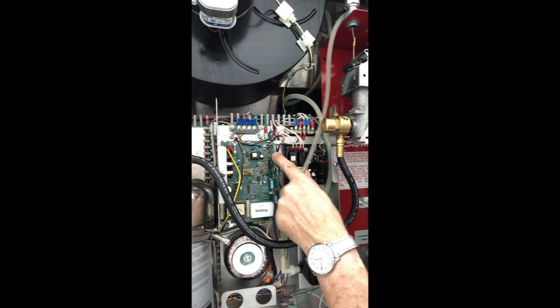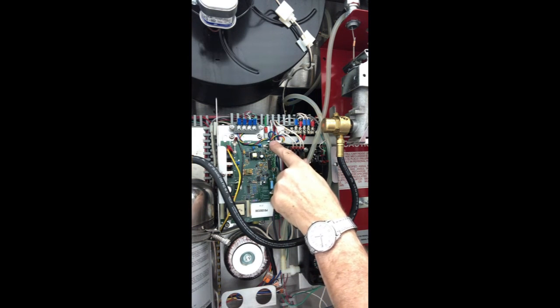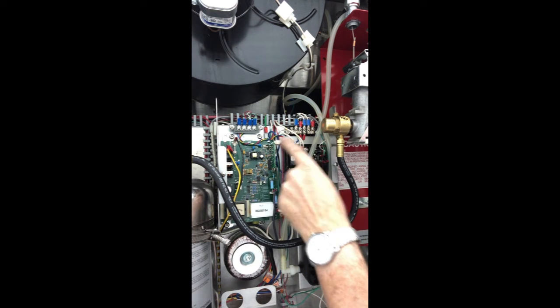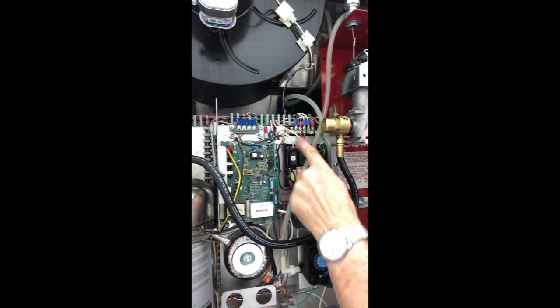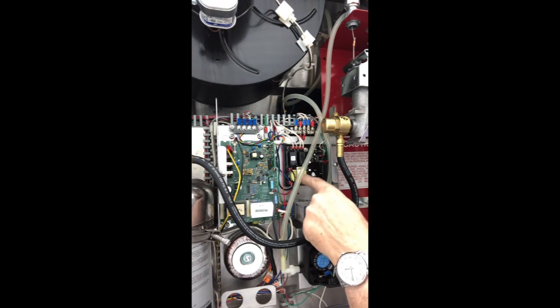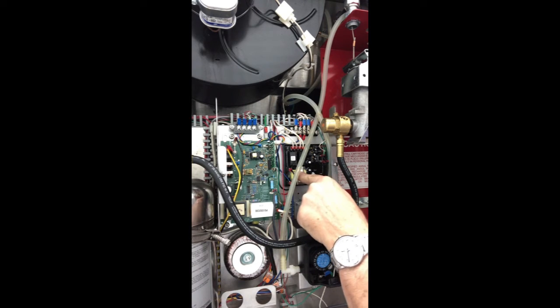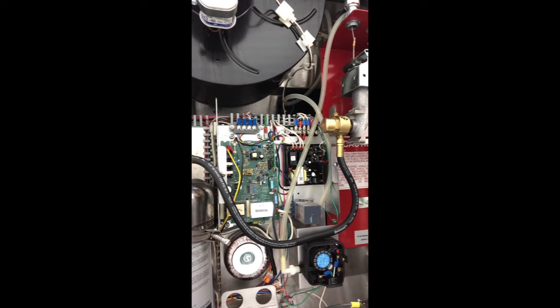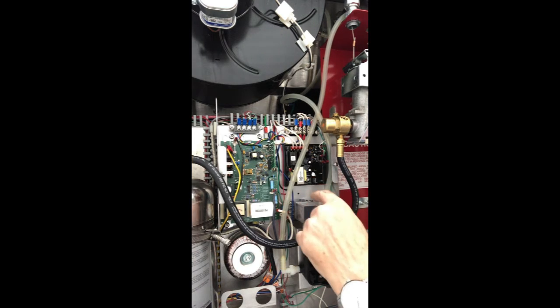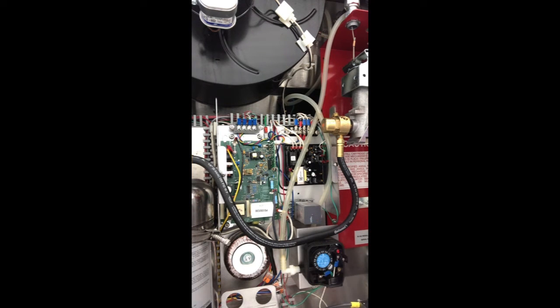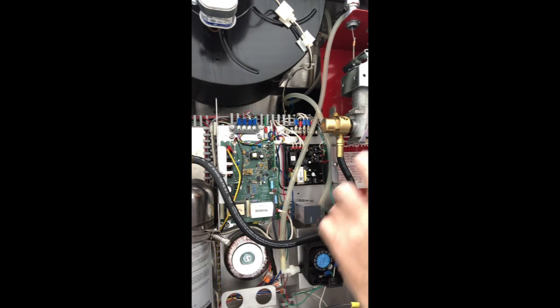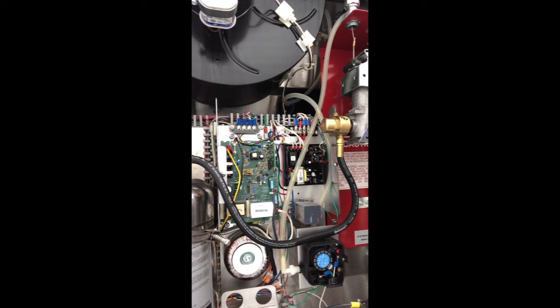And then this little board right here is what controls the DC output for our LEDs in the front. It also sends a signal over here to this board, which is our shutdown board. This board is the one that actually will drop your equipment out on larger hoods or just drop the heat elements out on units like this ventless fryer that I'm in now. Okay, if you have a digital controller on the front, it'll also work this relay. This relay is what sends the signal to that controller to tell it that there's an actual issue.